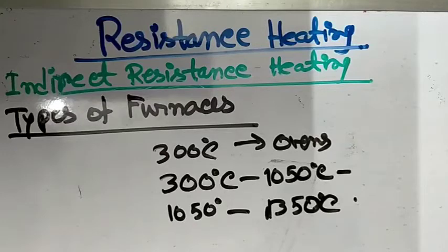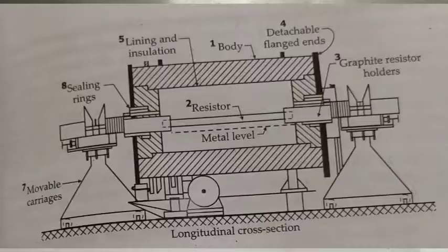If satisfactory means are provided to reduce the rate of oxidation to a minimum, to compensate for increased resistance as wear takes place, and to replace the graphite resistors easily and quickly when their useful life is complete, full benefit can be taken of the advantages of resistance heating over a high temperature working range. Here is a rocking resistor furnace as manufactured by Messrs. Birlec of England using graphite resistors. You can see it in this picture.